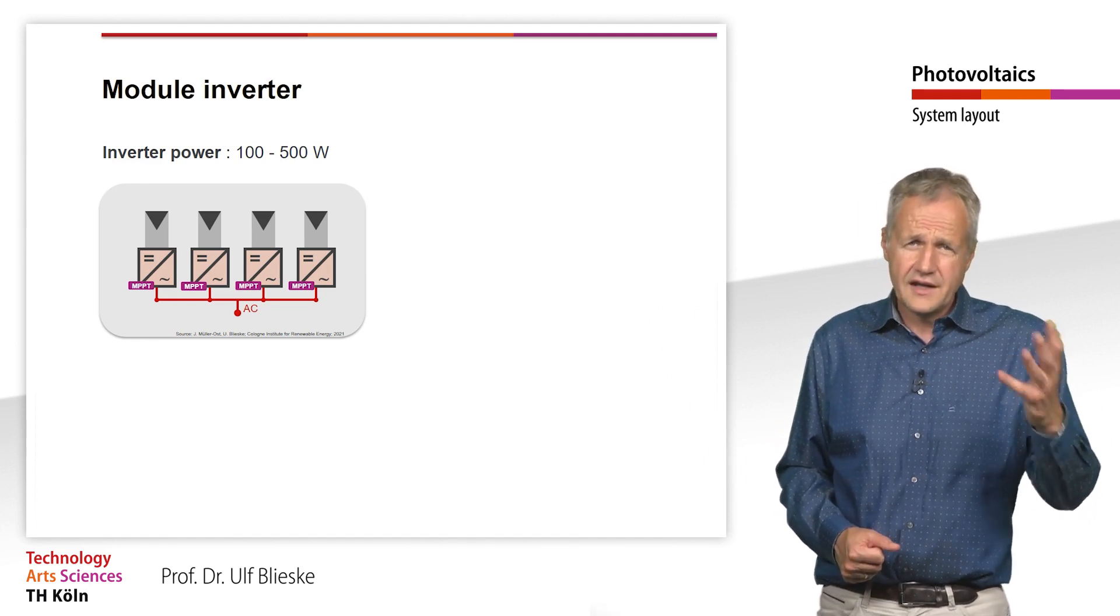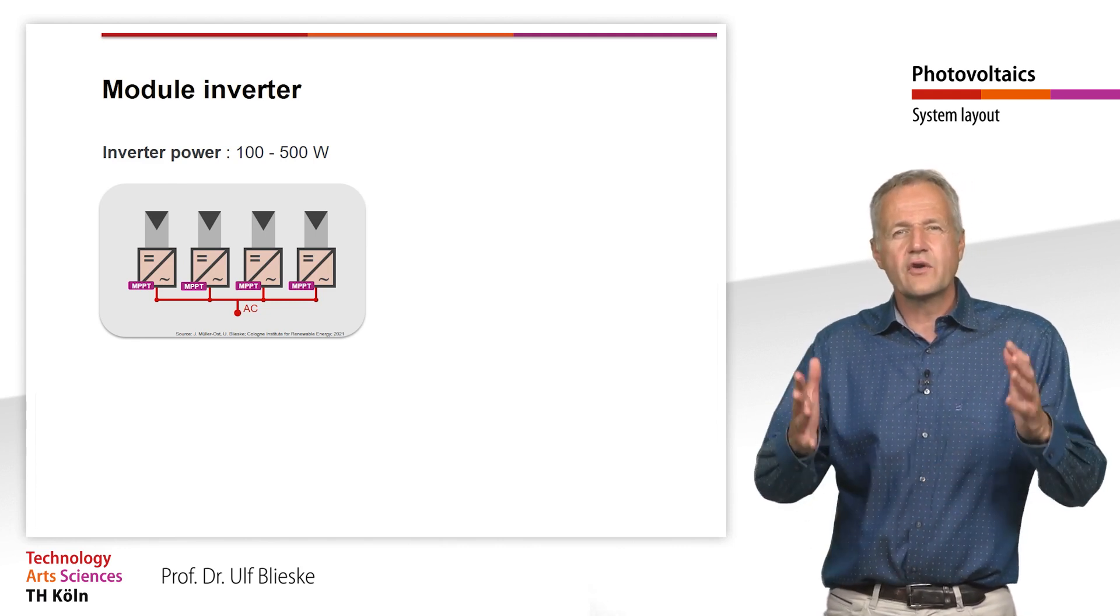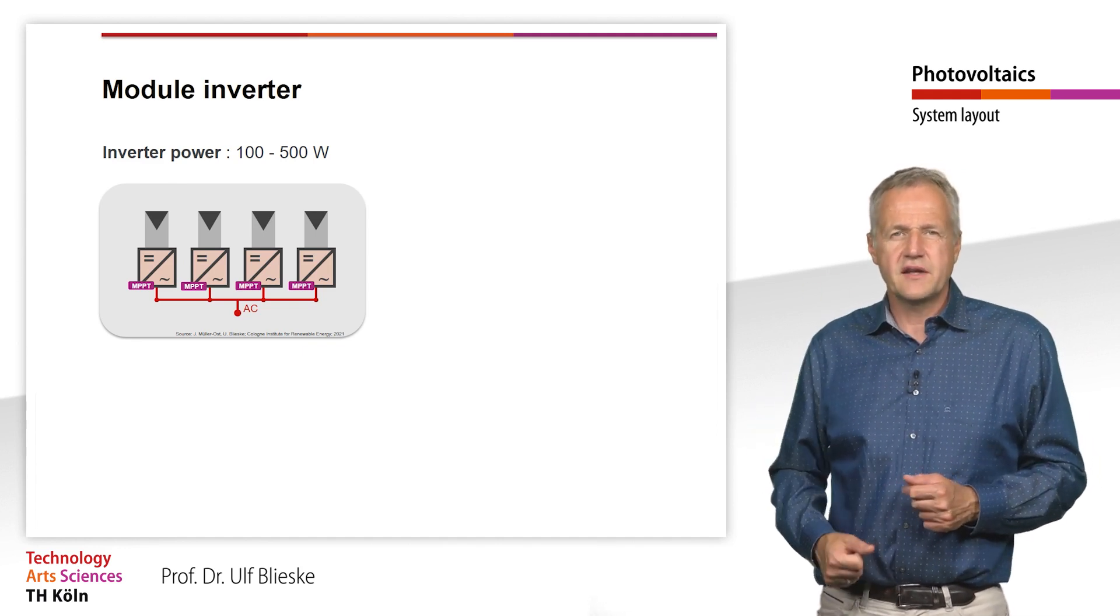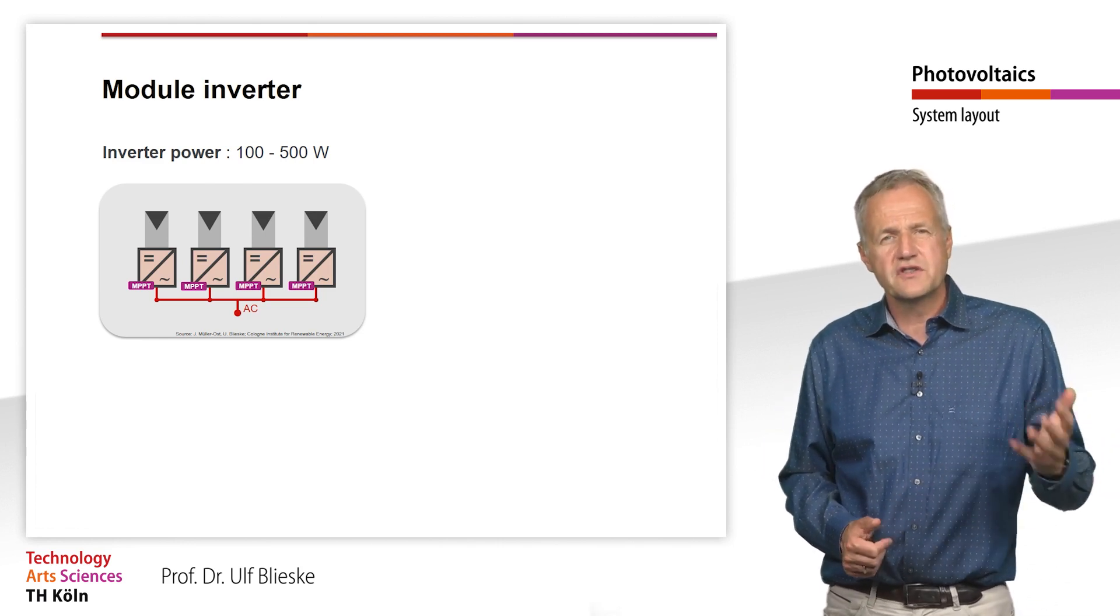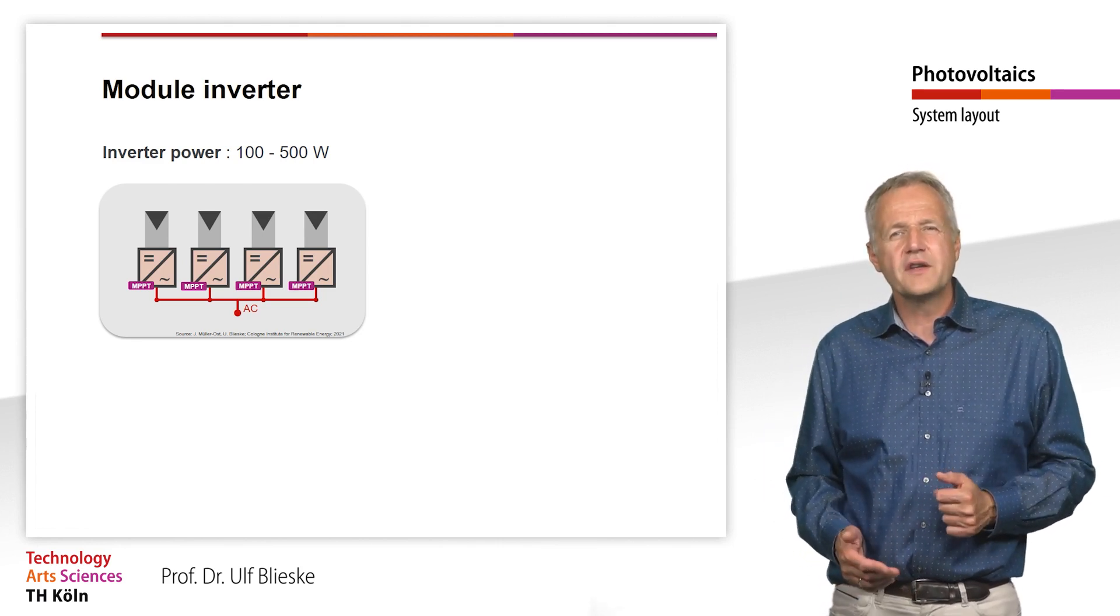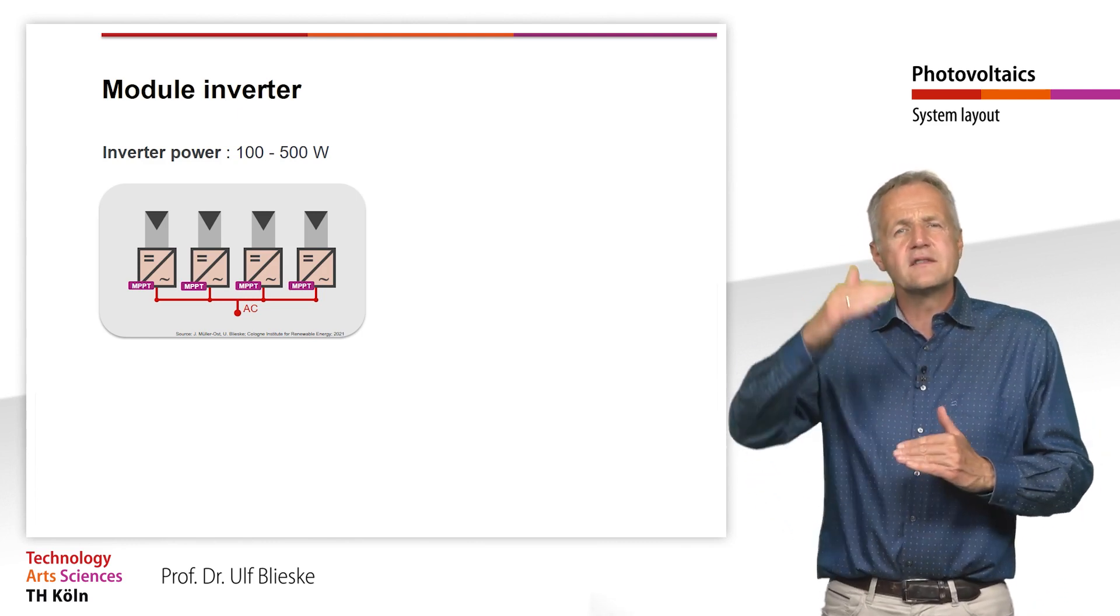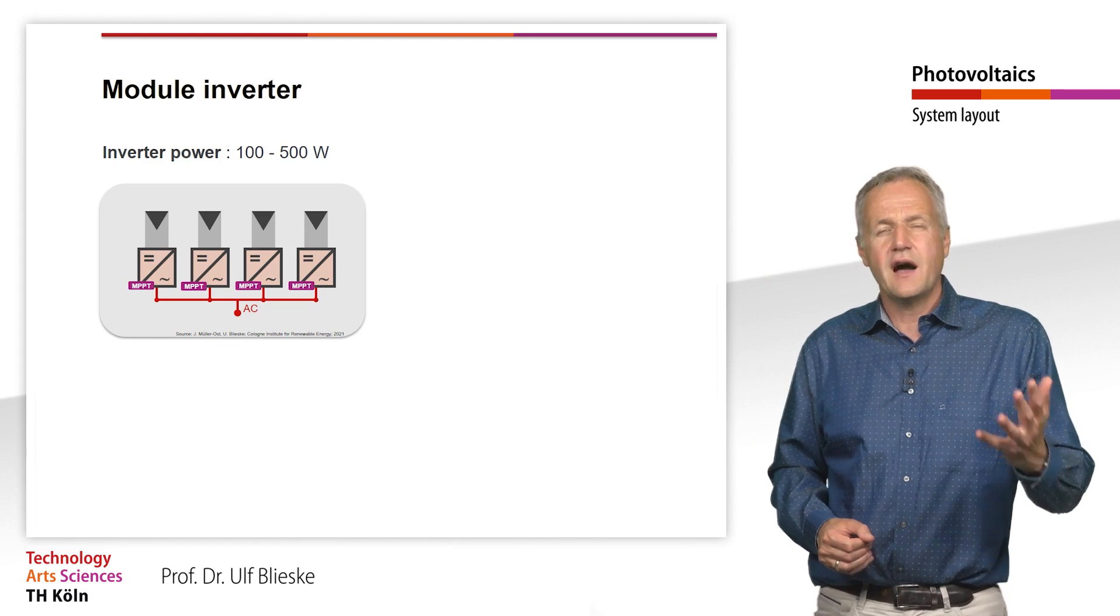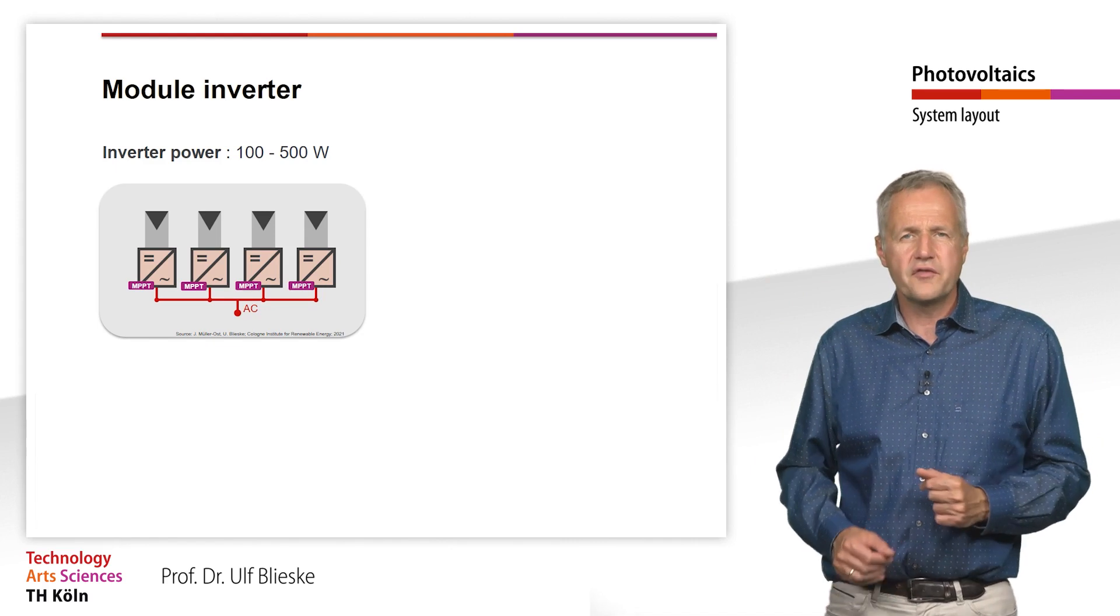With a string inverter, on the other hand, replacement is comparatively simple, since it is usually located at an easily accessible place and only one inverter needs to be replaced. Another disadvantage results from the low voltage of a single PV module, which is typically around 34-40V. Module inverters are therefore always two-stage devices with boost converters. Due to the immense difference between input and output voltage, the losses in the boost converter are comparatively high, which leads to a somewhat lower overall efficiency of the inverter.